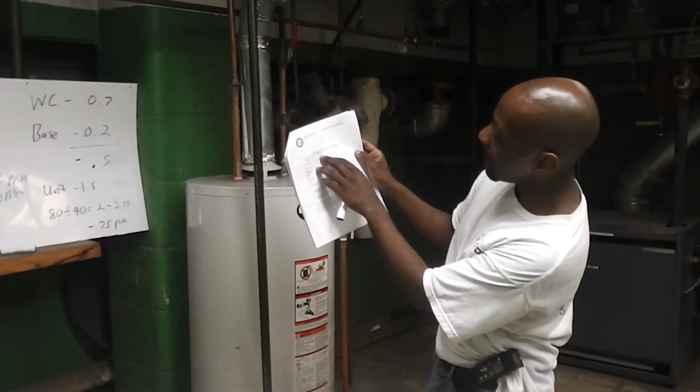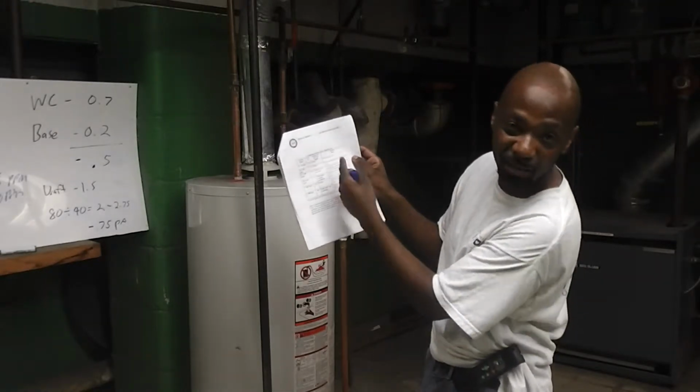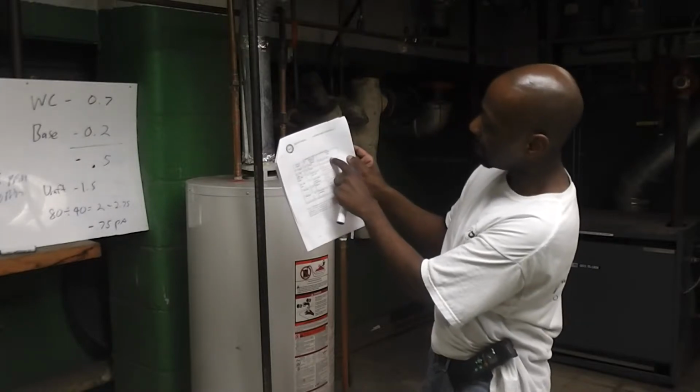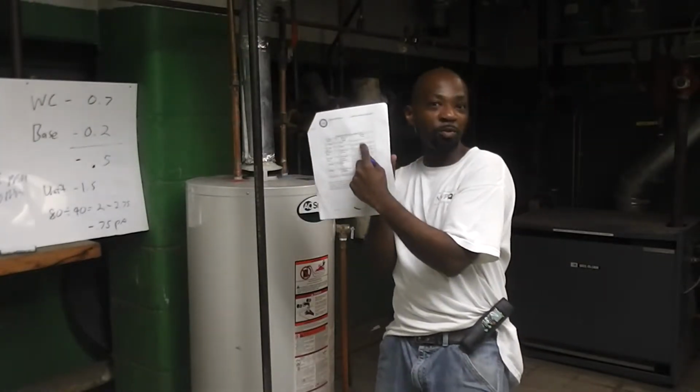It looks like we've passed the spillage and the draft test. So I'm going to look at this first line. That's what our results say. And it says retrofit action, proceed with work. I can continue working. So far we're doing pretty good.